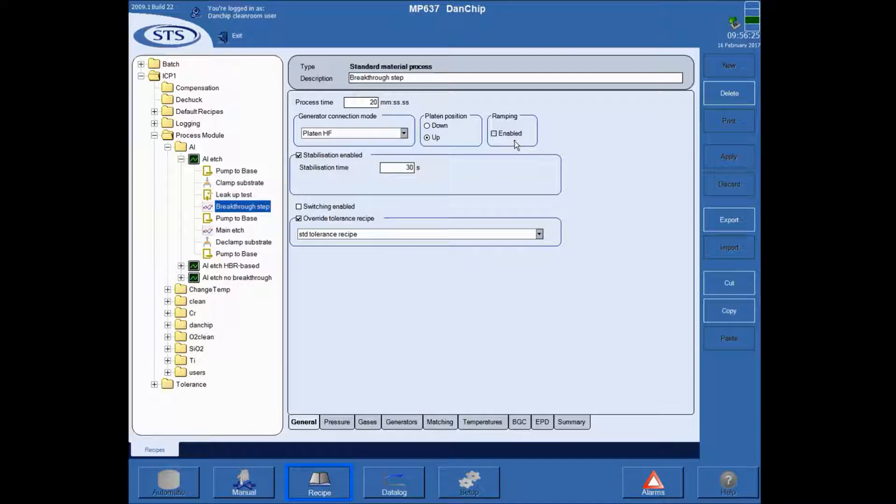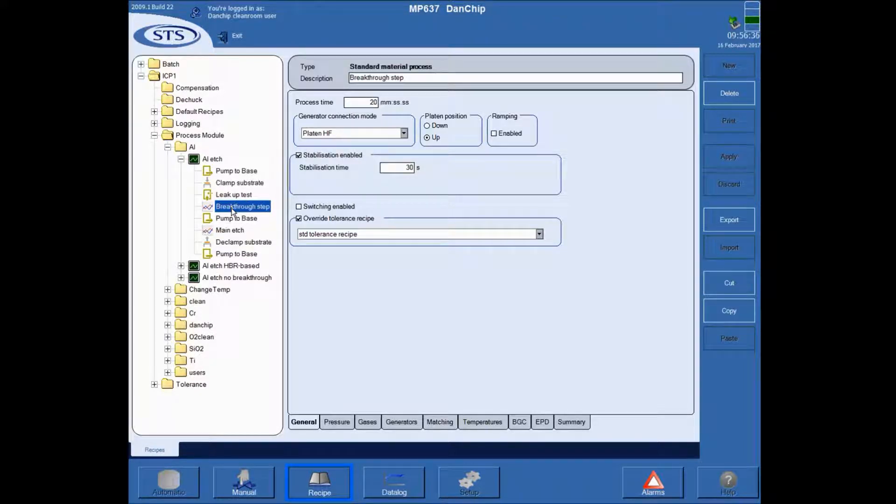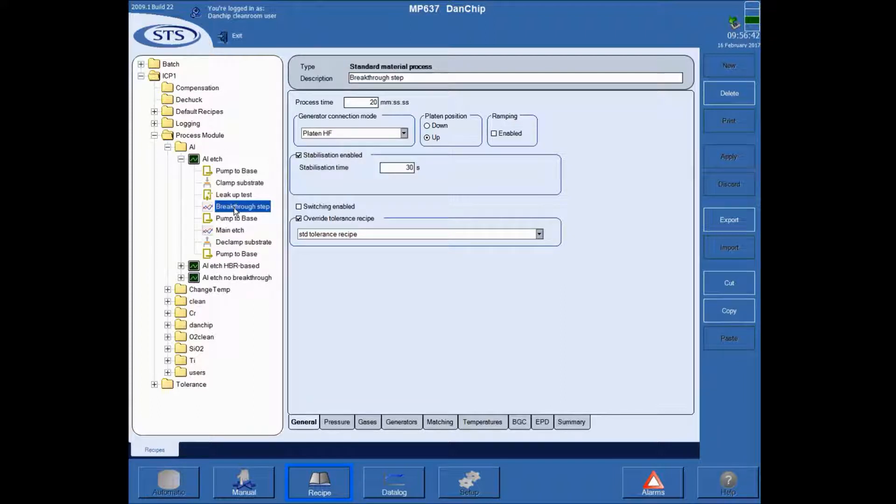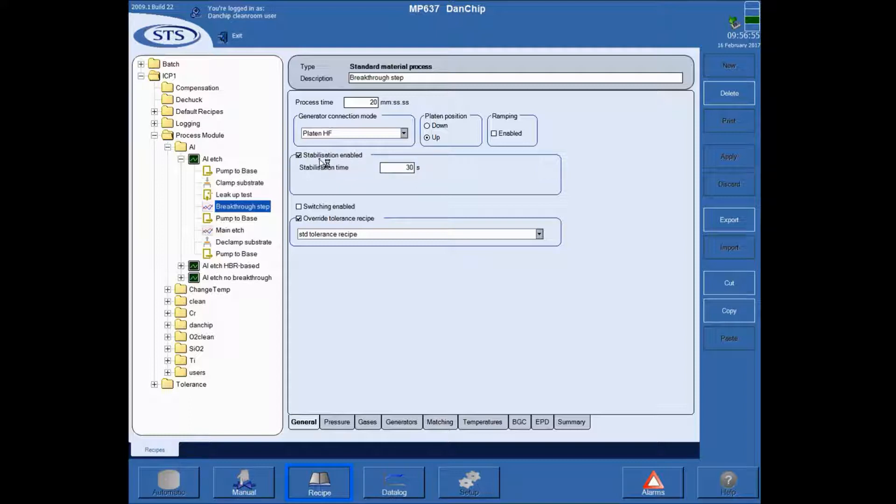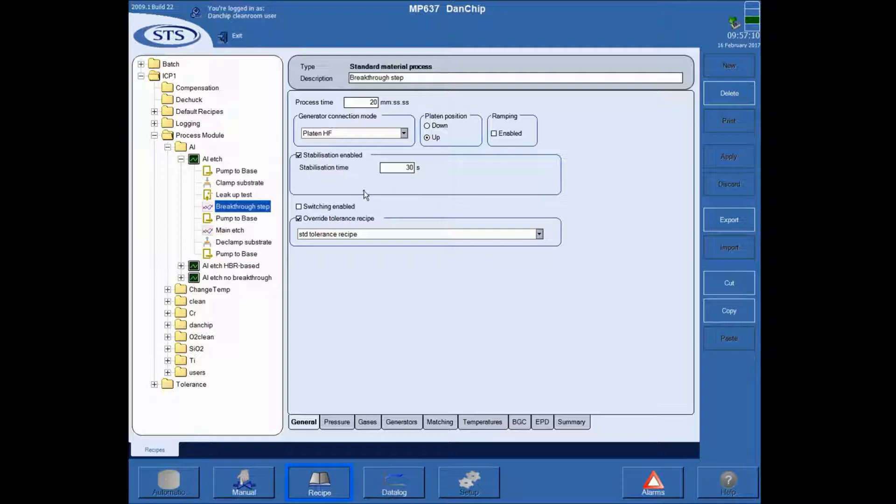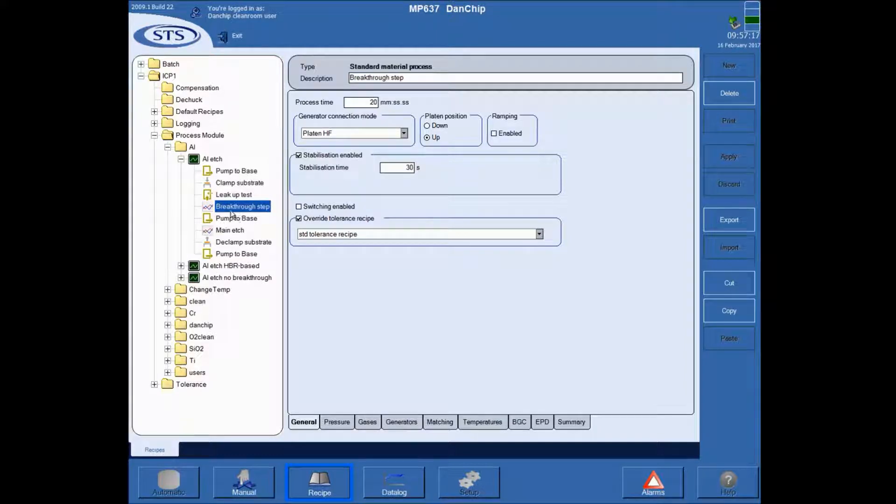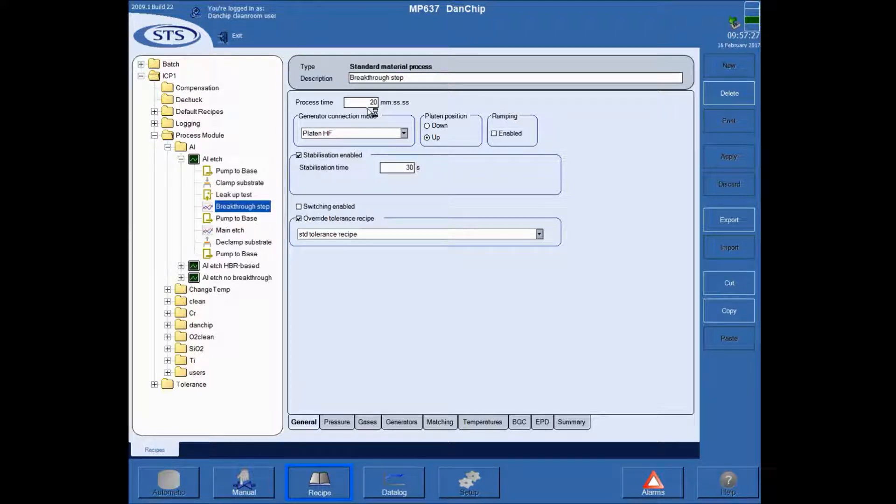The stabilization is very important because when you start a process step, you put on the gas and try to achieve the pressure that is indicated in the recipe. Once that has been established, it will stabilize for some time before it puts the RF powers on. If the stabilization is zero, then the gases will come on, the pressure will try to stabilize, and the RF powers go on at the same time. And that will cause the process to fail because it cannot achieve a stable plasma under those conditions. So you should always have a stabilization. Switching is for batch processes, but typically under general, you only change the process time.